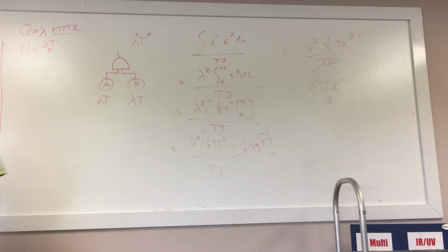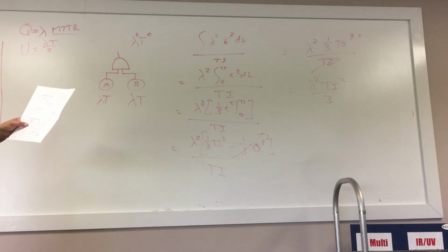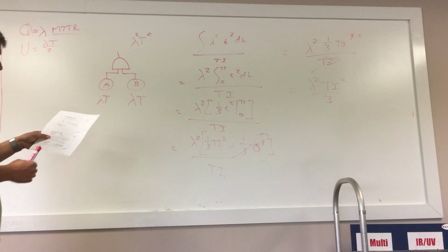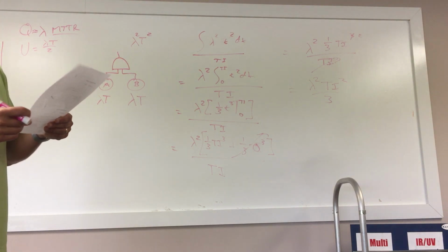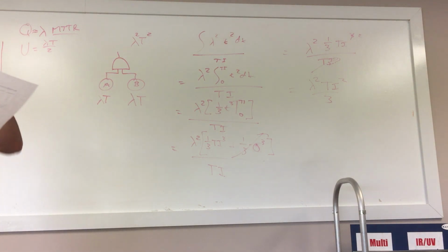So, continuing on in the equations, that's where the lambda t over 2 came from for the du term for 1 out of 2 voting. For the lambda dd term, I'm not going to derive it, but basically it's just doubled because you have 2 devices.